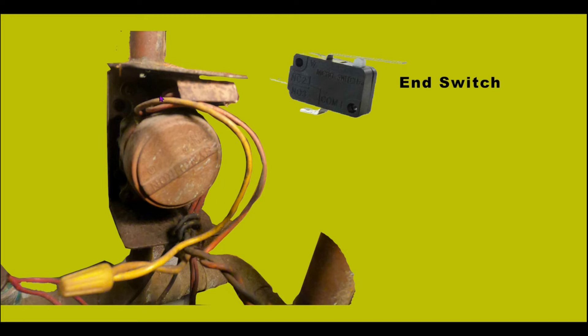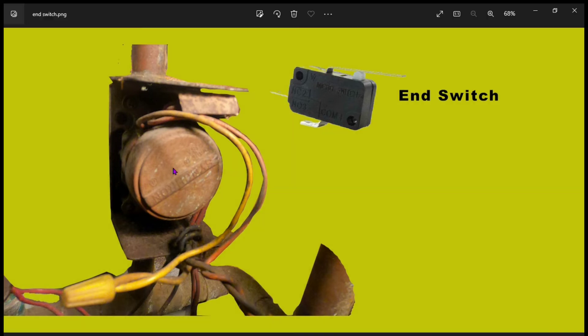Once power is applied to this motor via the thermostat, it moves an actuator which allows the flow of water to go to that particular zone. In addition to that, it triggers this end switch.